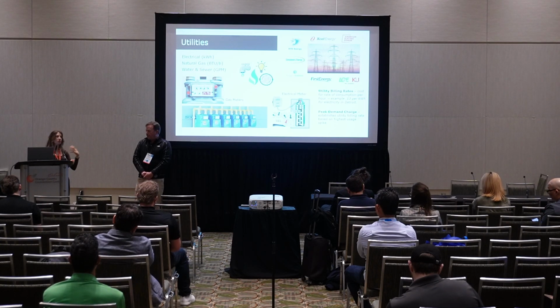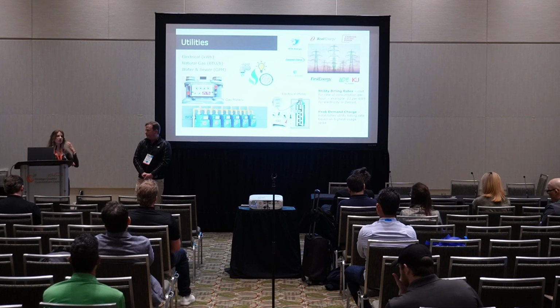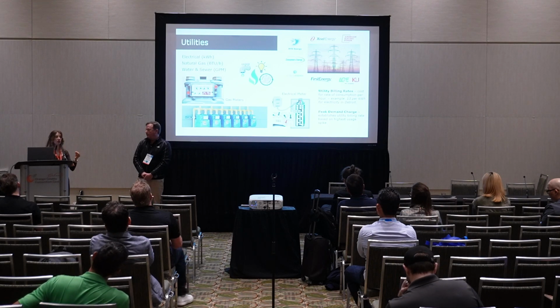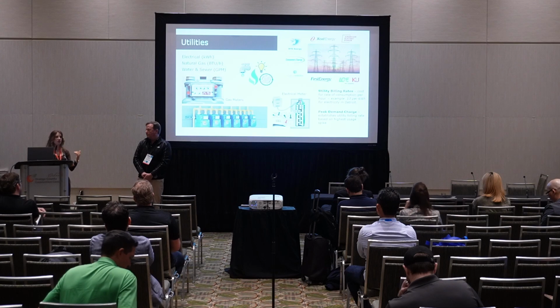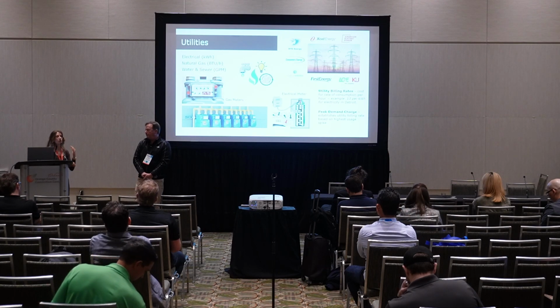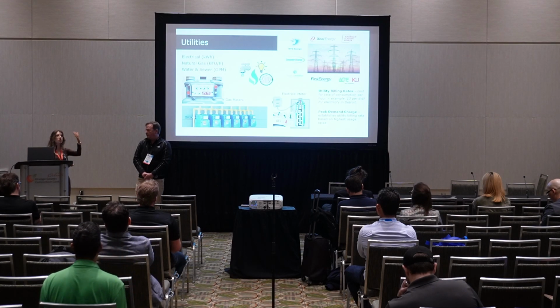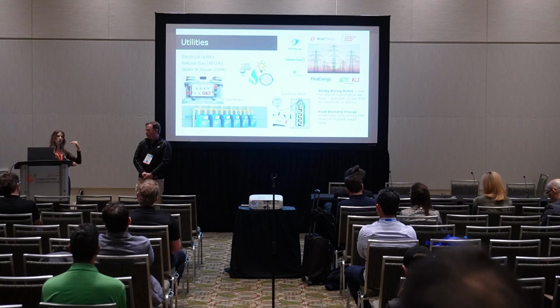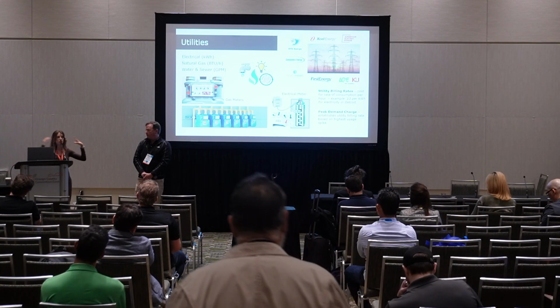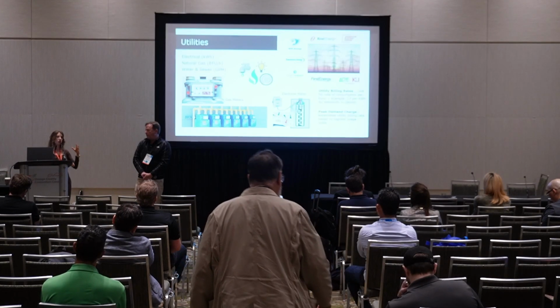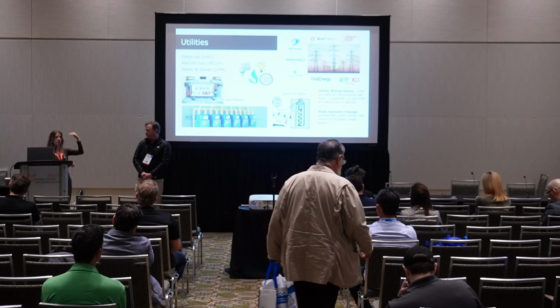That's more of a load management strategy - knowing when my peaks are and updating my sequences and the way I run my building so my peaks don't all stack on top of each other. Whereas demand response is triggered by the utility saying 'hey, this is a peak, I need you to drop now,' or you look at your peaks and drop. So it's in response to an external trigger, as opposed to a general change in strategy to ensure your peaks don't stack.